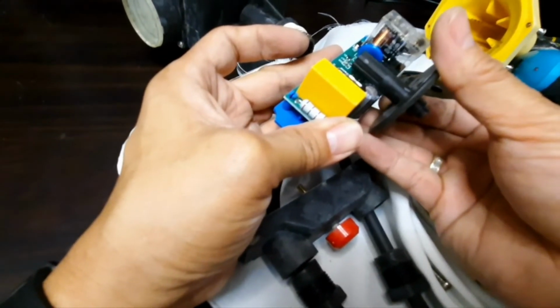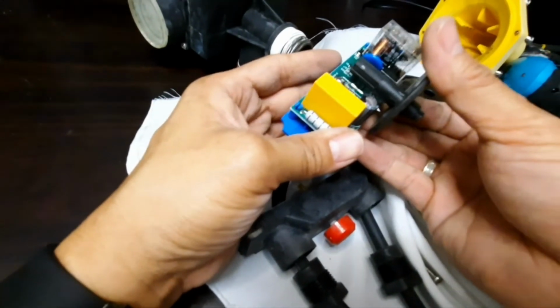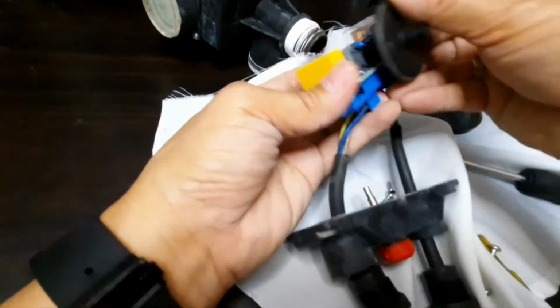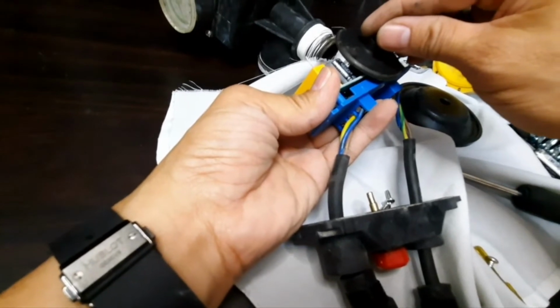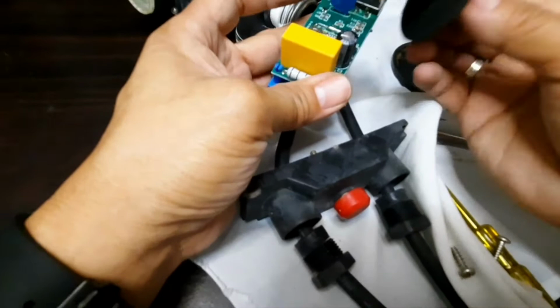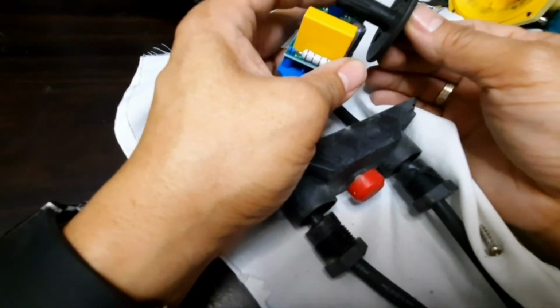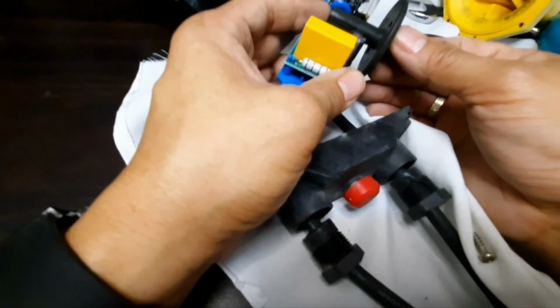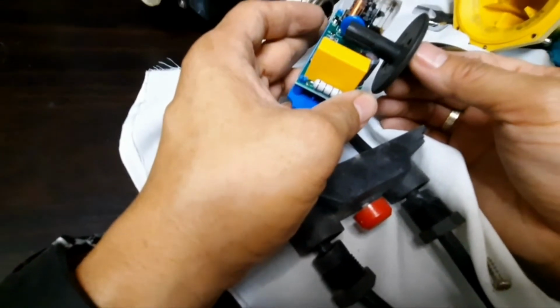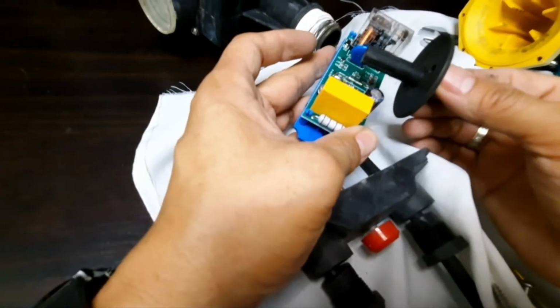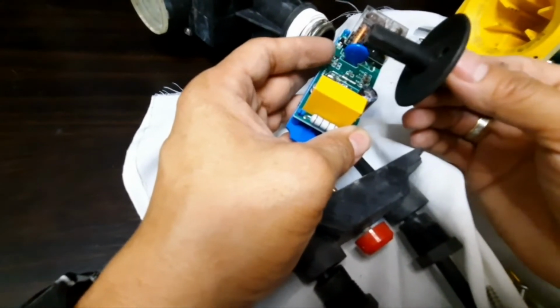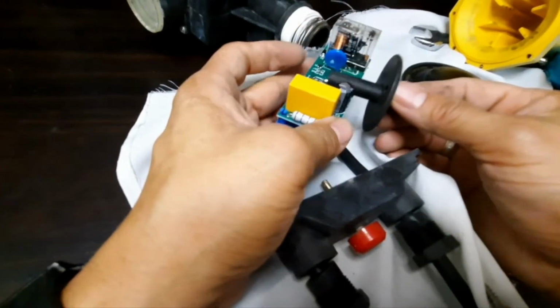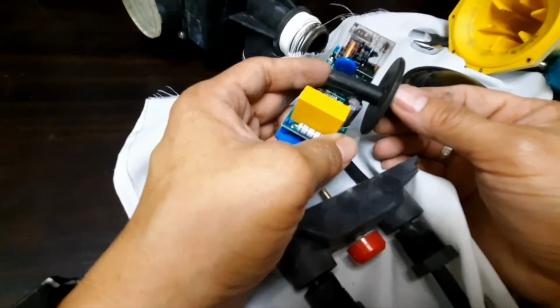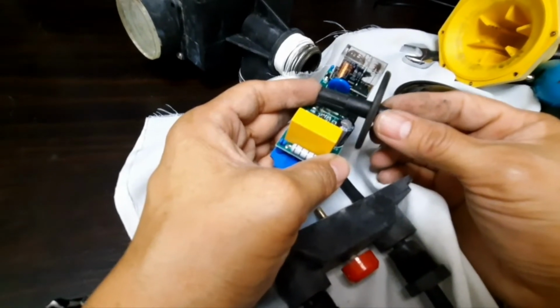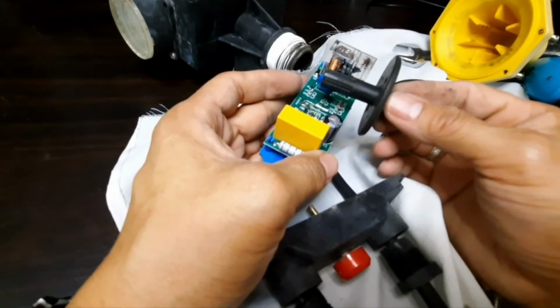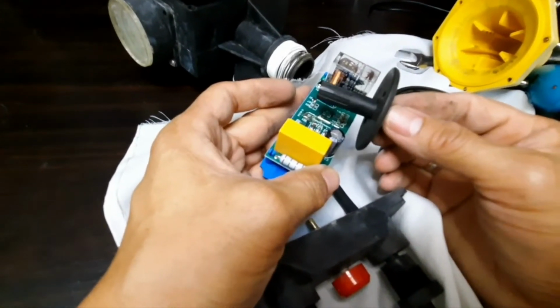So when it is too low, suppose there is no water inlet or water pressure, this sensor will position this way, like this. Okay, so basically the system is simple. There is a level sensor. Okay, that level sensor works from pressure. So if the pressure is low, it will give signal to the control to turn on the pump. But if there is no pressure at all from the inlet, the pump will trip, will turn off, in order to protect the motor. Because if the pump motor runs without water, it will burn the seal and later overheat and end up damaging the motor or the winding of the electric pump.